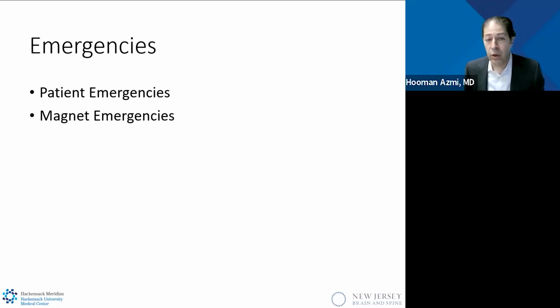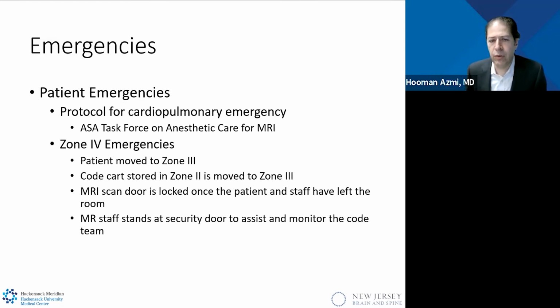And then certainly emergencies. If there is an emergency, what do we do? The emergencies can be divided into two separate categories: patient emergencies and magnet emergencies. For patient emergencies, there already is a protocol from the American Society of Anesthesiologists for cardiopulmonary emergencies, and this is detailed, and this is what we follow. Again, thank God we have not had to so far, but we are aware of the steps. The patient is moved to zone 3. The code cart, which is in zone 2, is moved to zone 3. The MRI scan door is locked once the patient and staff have left the room, and MRI staff stand at the security door to assist and monitor the code team that comes to zone 3.